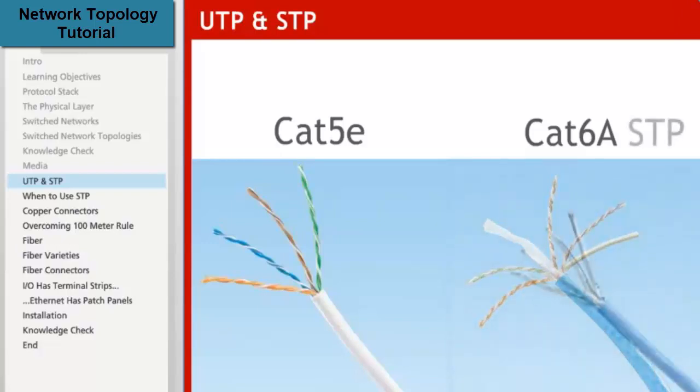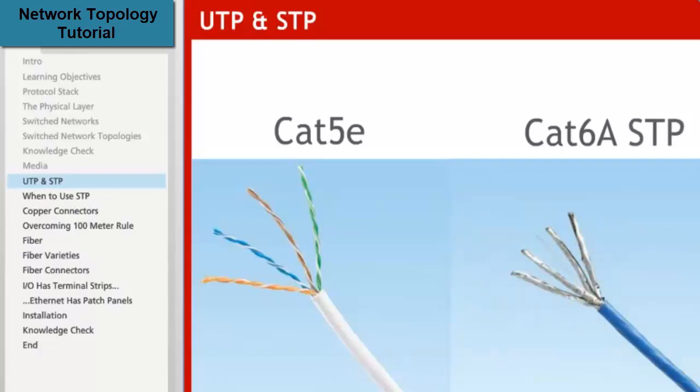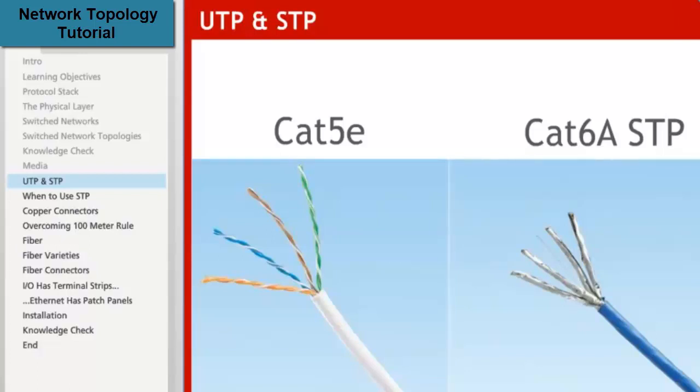Shielded twisted pair, or STP, is similar in construction to UTP but adds foil or braid shielding. Rockwell recommends that shielded twisted pair be used in high noise environments and always to connect motion and drives. The construction of a shielded cable is more complex and therefore not as flexible. Both UTP and STP are subject to the same distance specifications with a maximum channel length of 100 meters.